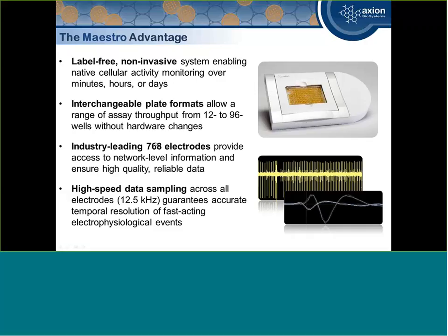We have 768 channels across all of our plates that allow us to get network level information and also ensures high quality, reliable data. We have a very high data sampling rate of 12.5 kilohertz, which guarantees good temporal resolution on all electrophysiological events where action potentials occur.